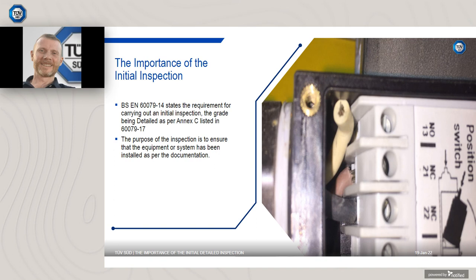Initial inspection should encompass the physical installation as well as a check of engineering documentation. The documentation should be included in the master dossier. The detailed inspection and testing should be in accordance with IEC 60364-6. BS EN 60079-17 supplements the requirements of this.